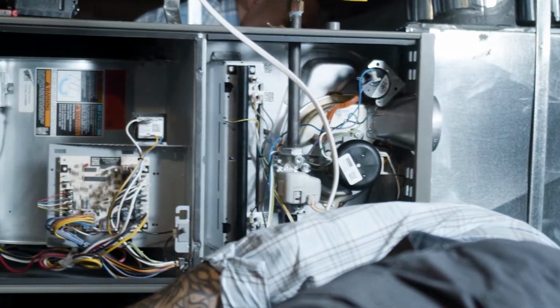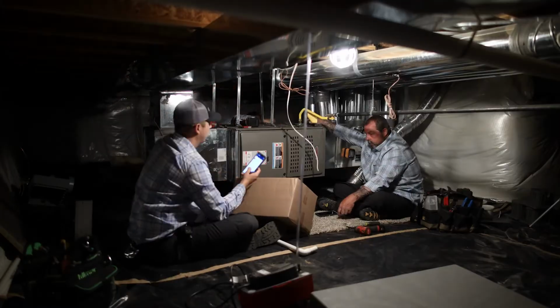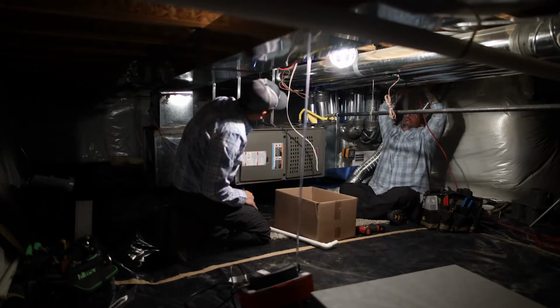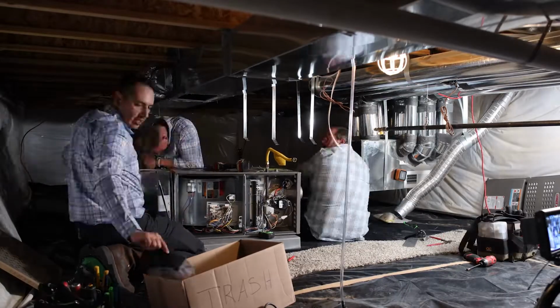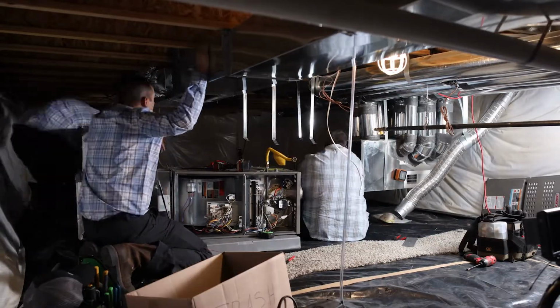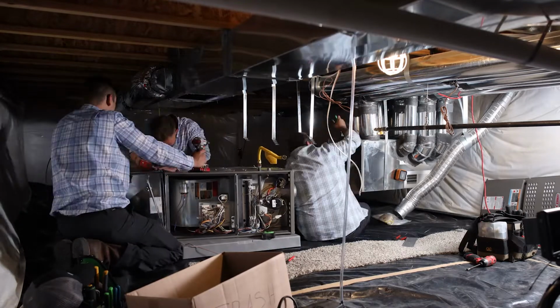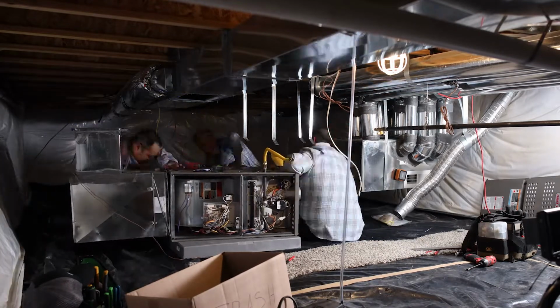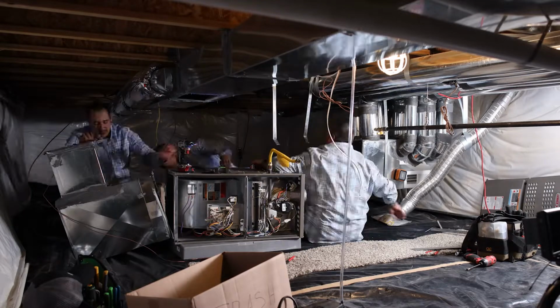We're gonna completely drop the furnace and the return ductwork. We're gonna have to reinstall the furnace and we'll set a pad, get it all leveled out and put some risers on it so we can level the furnace and the coil. So we'll get all that set up and then reconnect everything to the existing ductwork.